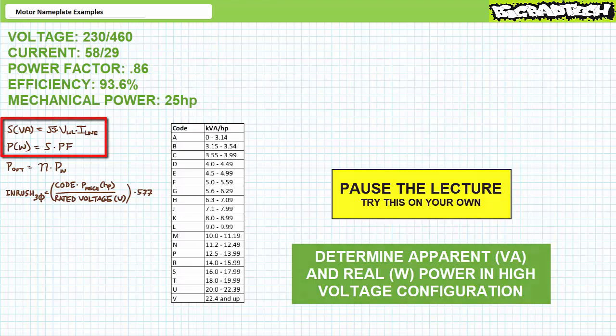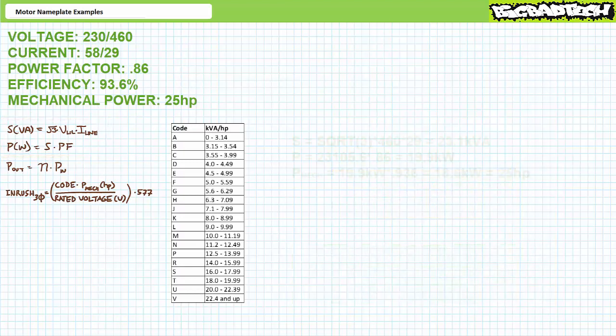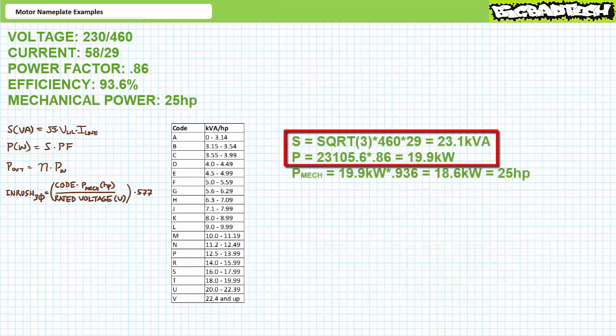If you're tracking, you should obtain the following data. Substituting our given values into the apparent power formula demonstrates apparent power input equals 23,105.6 volt amperes, or more appropriately 23.1 kilovolt amperes. Substituting our given values into the real power formula demonstrates real power input is equal to 19,870.8 watts, or more appropriately 19.9 kilowatts.